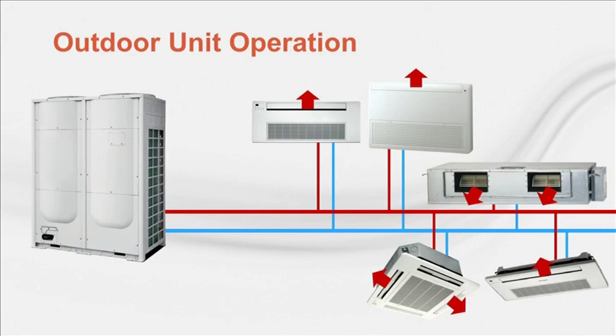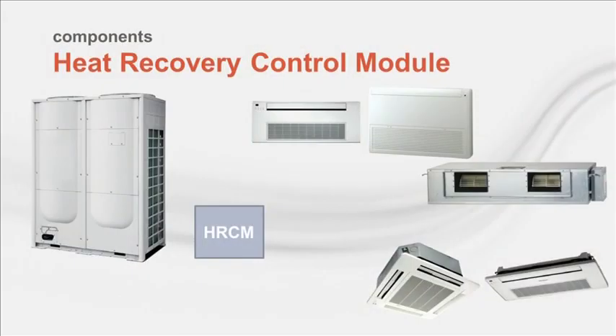In this mode, the heat exchanger in the outdoor unit serves as the evaporator. Heat pump VRF systems either operate to provide cooling or heating. They cannot provide both at the same time. On the other hand, heat recovery systems have the ability to provide simultaneous heating and cooling because both high-pressure gas and liquid refrigerant are available to the indoor units. The heat recovery control module, shown here as a gray box, enables the system to provide both heating and cooling simultaneously. For heat recovery systems, the control module acts like traffic police in that it's able to direct either hot gas or liquid refrigerant to the individual indoor units.